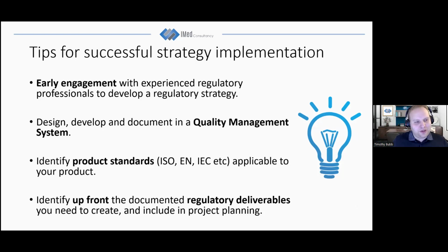I'm now going to move on to a few tips. The first one is really early engagement. Make sure that you're understanding what the regulatory strategy is for your device. Second one, quality management system. Make sure that you've got one in place and that you're designing and developing within that system, particularly for medium and high risk products, which require you to have a quality management system and to have what's called design controls within that system.